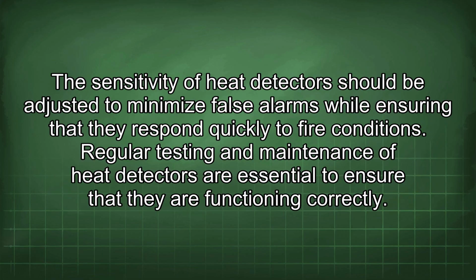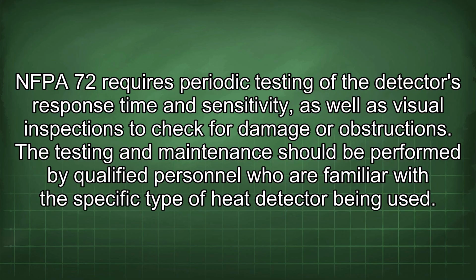The sensitivity of heat detectors should be adjusted to minimize false alarms while ensuring that they respond quickly to fire conditions. Regular testing and maintenance of heat detectors are essential to ensure that they are functioning correctly. NFPA 72 requires periodic testing of the detector's response time and sensitivity, as well as visual inspections to check for damage or obstructions.